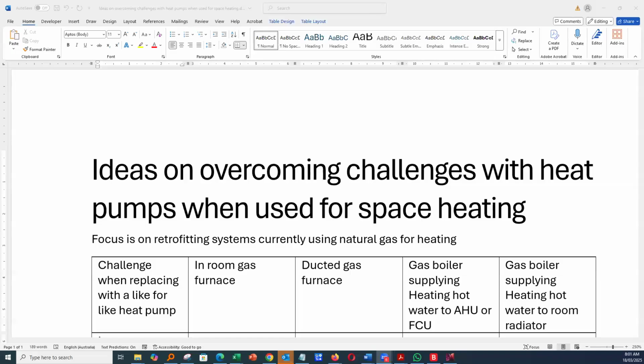So basically, with different gas systems, I guess you could say we have four different types of systems. We can either have a gas furnace, which basically just heats air, and that gas furnace is located in the room. We could have a gas furnace which is ducted, with air ducted into the room. Maybe that gas furnace would supply multiple rooms. A fourth possible configuration is where we have a gas boiler that supplies heating hot water to air handling units or fan coil units, basically just radiators with air flowing over them. And then finally, we could have a gas boiler supplying heating hot water to a room mounted radiator. They're the main ones. Of course, there are others, perhaps hydronic heating, underfloor slab, stuff like that. But let's just focus on these four, which are typically the ones that you find in commercial buildings. And I've got more of a commercial building focus here.